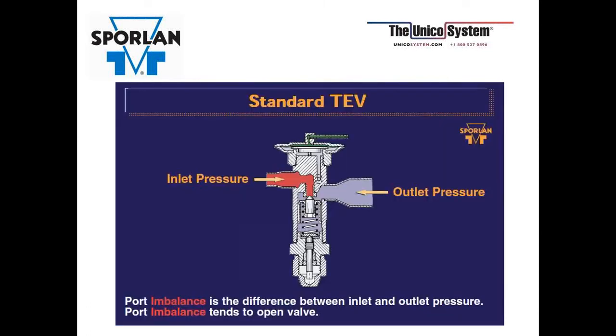A standard TEV would have a pushrod system, and what you have here is the inlet pressure that's sitting on top of the pin, and the outlet pressure underneath the pin. So obviously your inlet pressure is going to be high pressure, higher than the low side pressure. So you're going to have a port imbalance, and that's the difference between the inlet and outlet pressures. So port imbalance will tend to open the valve.